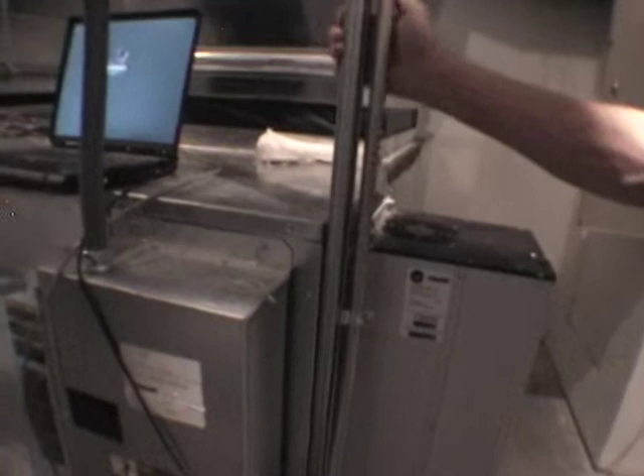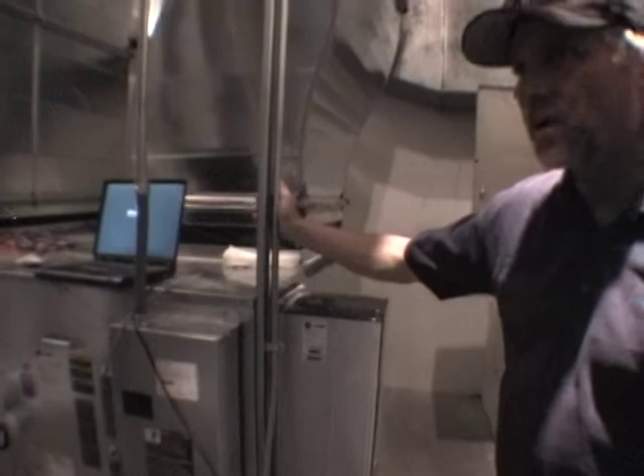These are the variable speed drives supplied by the mechanical contractor. They do not have a LonMark card in them, but we can adjust the speed from our LON controllers, and we can perform a start-stop. Because the primary issue in many churches is noise, we want to be able to adjust the speed of these air handlers to deliver enough air, but at the quietest speed possible.